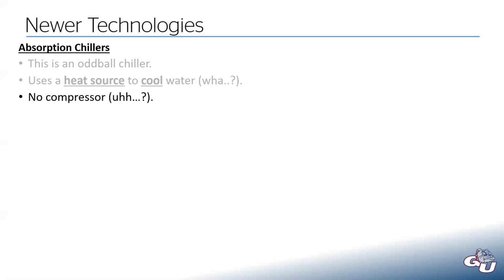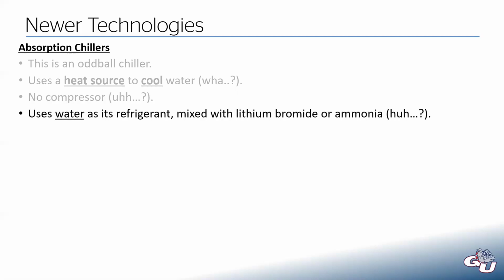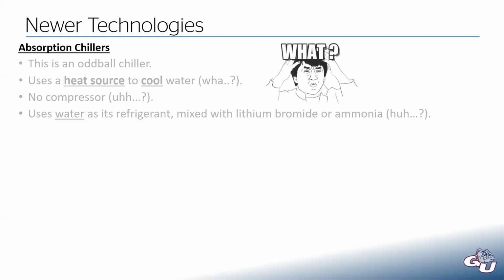There isn't a compressor. So there's no compressor driving a refrigerant process between the evaporator and the condenser. Well, that's totally different from every other chiller. It actually uses water as its refrigerant liquid mixed with some lithium bromide or ammonia. Well, that's not like any other refrigerant we use in any other chiller or air conditioner. So everything about this just screams, what is going on with this chiller? Why is this one so different from every other chiller, or at least from a traditional chiller? So what's going on here?